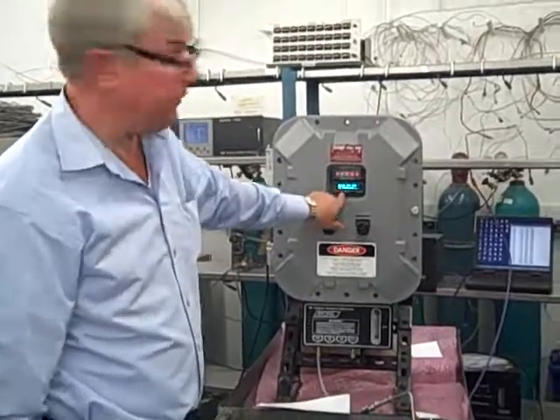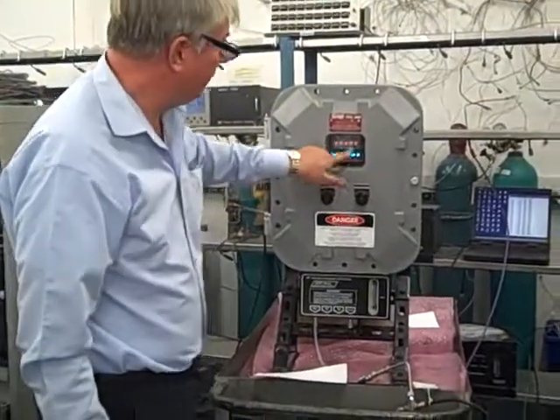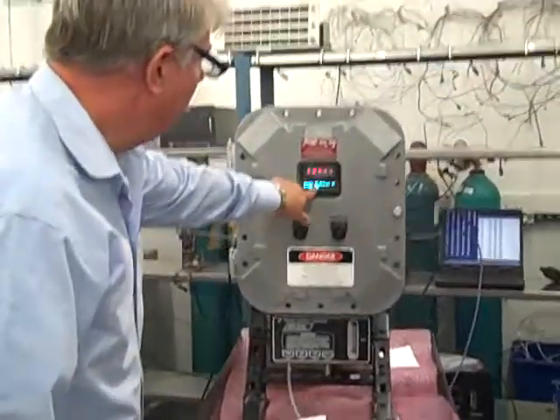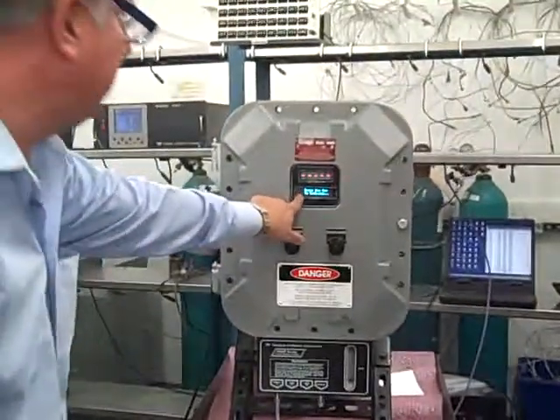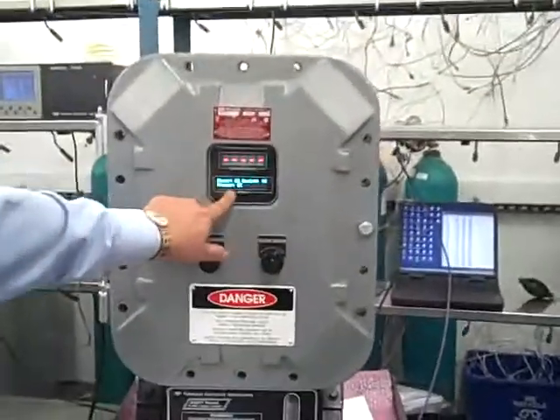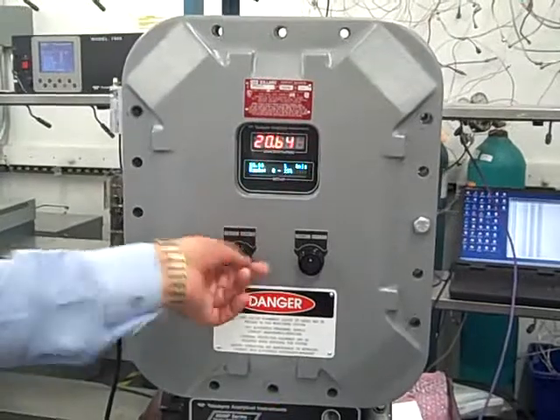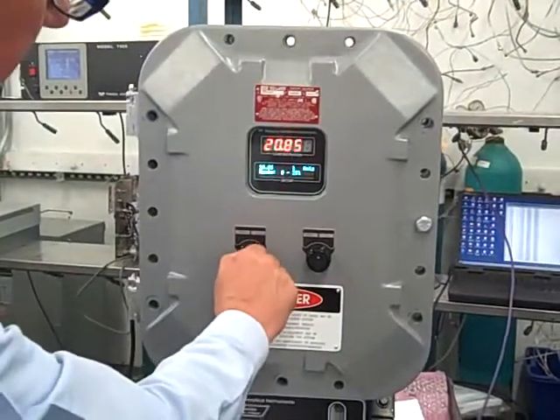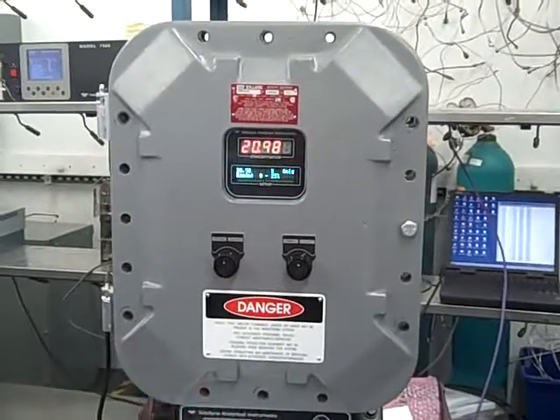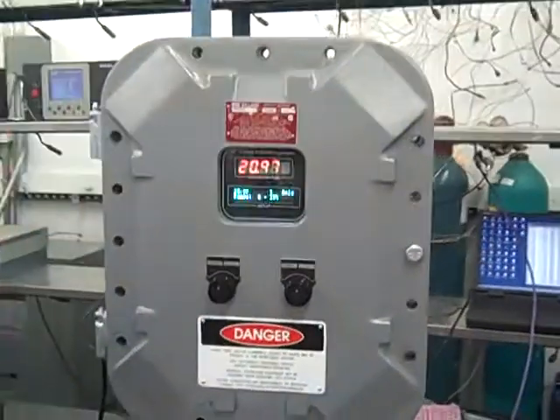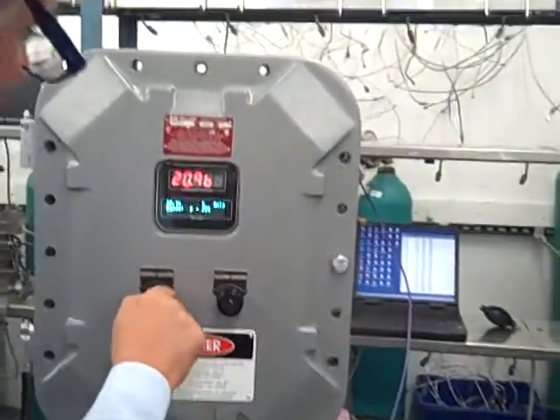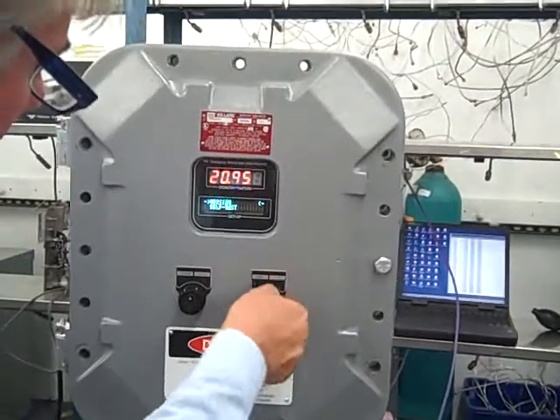Well, in this case, it didn't take that long. Took very little time. So we have OK on all of the things. Power is OK, analog outputs are OK, and preamp OK. So we press any key to continue. Now let's scroll down for the additional menu options. In a trace analyzer, it will take longer to test because of the large capacitors on the preamp board. Okay. So here we go.